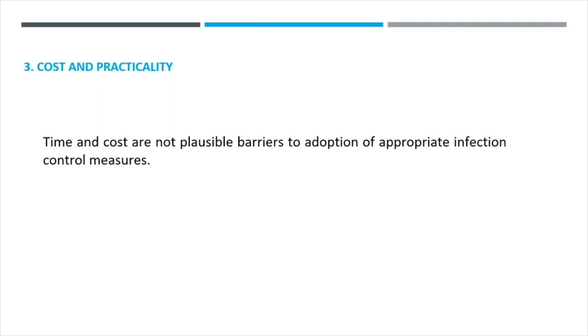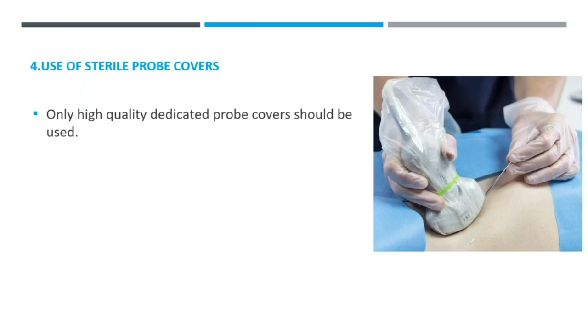Well, firstly, handmade covers and Tegaderm strips were never designed for this, and they provide an ineffective barrier and should never be used. Sterile probe covers aren't actually medical devices and are not covered under TGA legislation, so there's no clear definition of what they are. There is good research to show that dedicated probe covers made for the purpose have a very low, not a no, leak rate, and they also minimize the image degradation that they cause. And so our recommendation is that only high quality dedicated probe covers should be used.